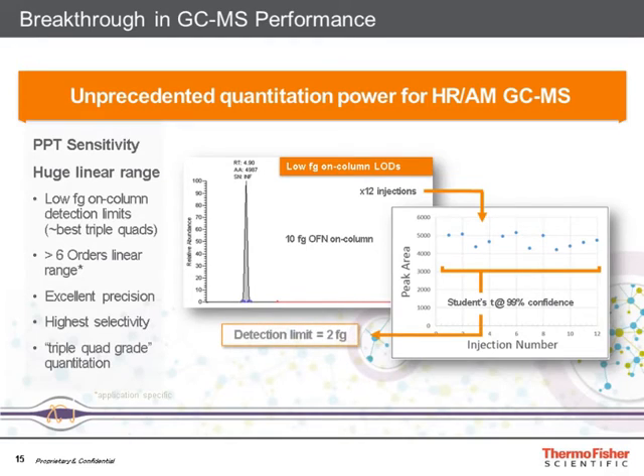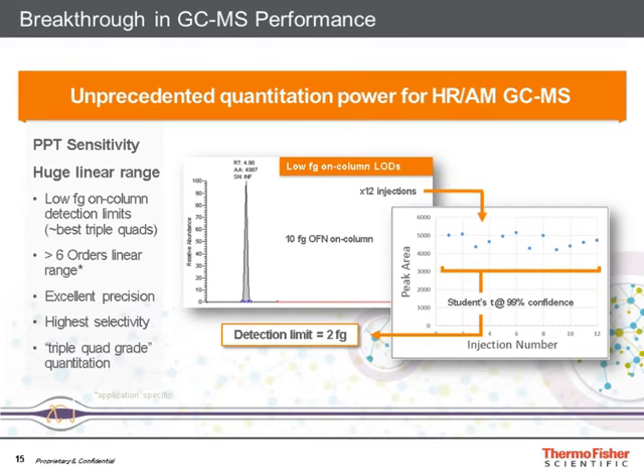This high resolution and mass accuracy is supplemented by exceptional sensitivity performance. We have a system suitability test that can be performed on every instrument, testing at very low levels — 10 femtograms of octafluoronaphthalene on column. Because of the exceptional resolution from the system, we don't really see any noise. We define our system's analytical performance based on a statistical evaluation of replicate data, and we believe that the detection limit for most analytes would be in the very low femtogram level. For octafluoronaphthalene specifically, it is 2 femtograms.